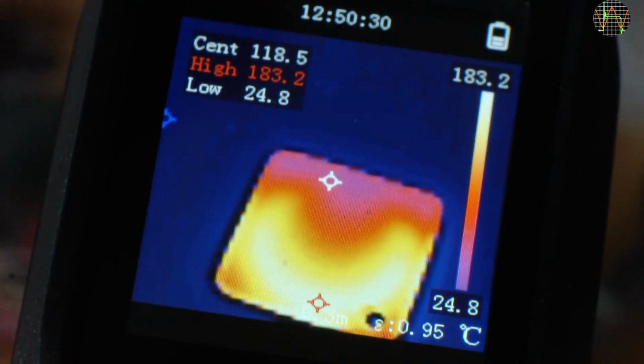As for accuracy of measurements, it is a tricky subject to get the emissivity right, the table in the menu notwithstanding. Usually the thing you are measuring is not in the table, and some tweaking may be needed by using a trusted reference. In this test, I left the emissivity at 0.95 but monitored the temperature of the hot plate with a thermocouple, which is the blue circle at the bottom right.